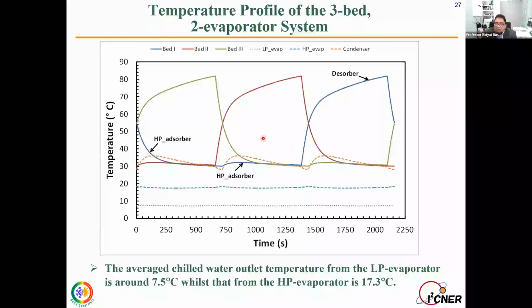So what kind of outlet are we getting? The average chilled water outlet temperature from the low pressure evaporator is about 7.5 degrees. So this one is our outlet temperature from the low pressure evaporator, and from the high pressure evaporator we are getting about 17.3 degrees. So we can use this temperature, from 16 to 22, for the process cooling application, and this is very good for our room cooling applications. And these are the temperature profiles of our beds when they are in adsorption. So high pressure adsorption is happening here, and when it is desorption, the temperature increases, and the profile is like this.